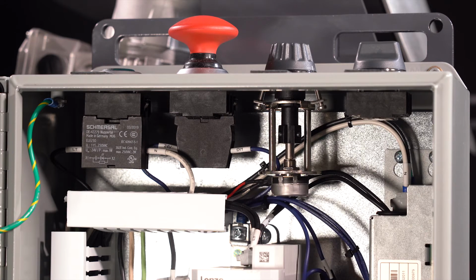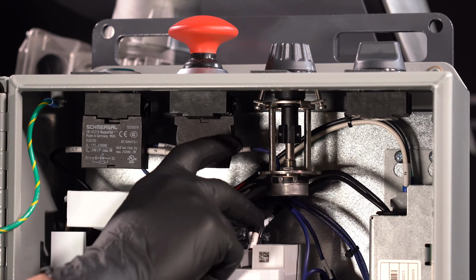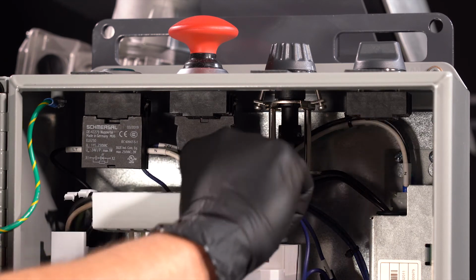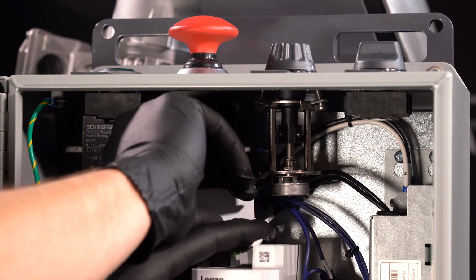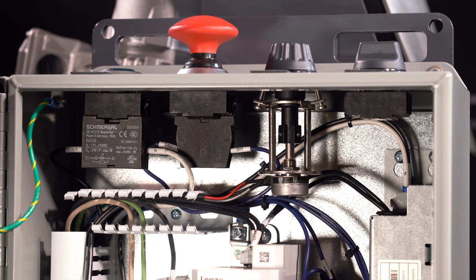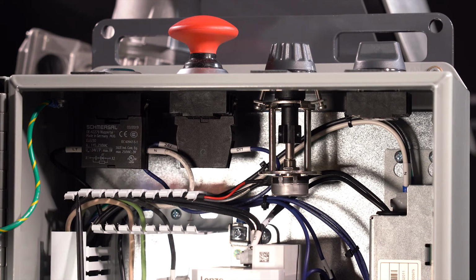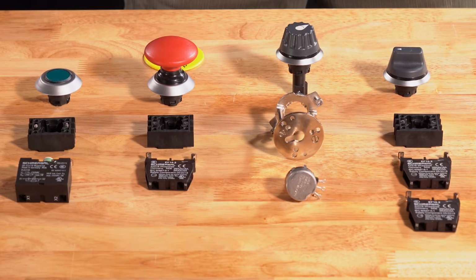Using a small flat-headed screwdriver, you will back out the screws on the mounting block in order to remove an electrical component. For the machine on light, you can feed your screwdriver up through the wire guard. Be careful not to disturb the wiring here. To illustrate how all this works, we've got all the electrical components associated with switches and buttons and lights laid out on the table to walk through.